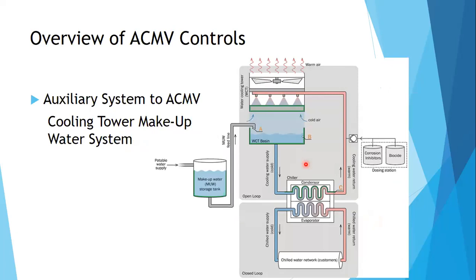Last one is your makeup water system. When your cooling tower operates, some of the water is vaporized or trickled down. When outdoor air goes inside, some of the water evaporates and some of the water goes with the air. So not all of the water that flows down goes back out. To compensate for the loss of water, you have a makeup water system. This makeup water tops up, ensuring that the water within the cooling tower is always at the optimum level.